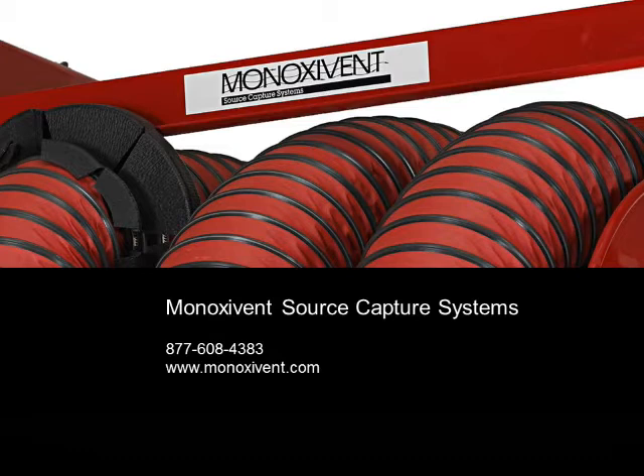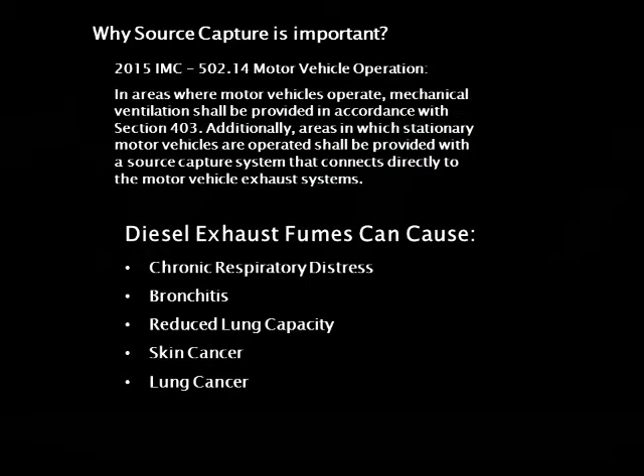There are many regulations federally that call for the elimination of vehicle exhaust. In particular, the 2015 International Mechanical Code says, in areas where motor vehicles operate, mechanical ventilation shall be provided in accordance with Section 403. Additionally, areas in which stationary motor vehicles are operated shall be provided with a source capture system that connects directly to the motor vehicle exhaust.